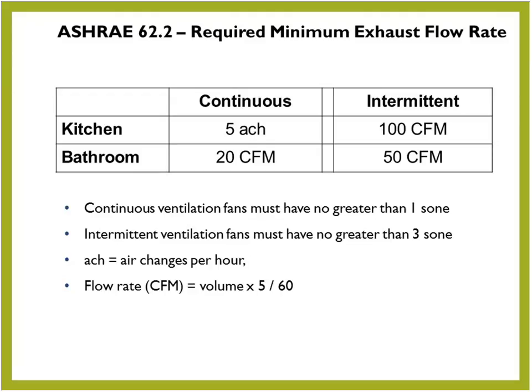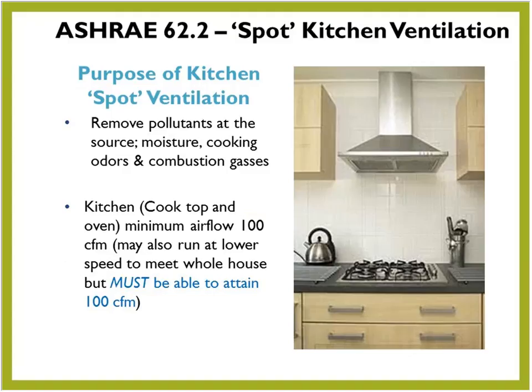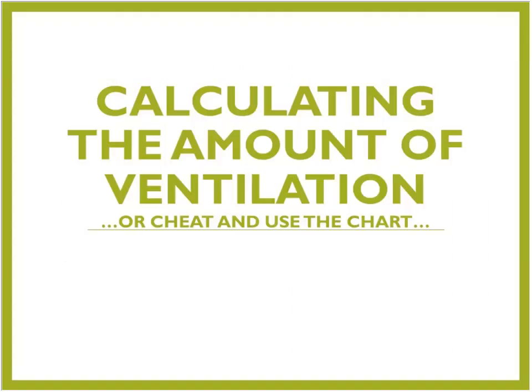Quickly, in terms of sizing those bathroom fans, there's a couple of different ways to do it. We recommend 1 CFM per square foot for the bathroom in order to exhaust that moisture quickly enough. There's other ways too, like you see here, the calculation V times 5 over 60. So the volume, length times width times height of the bathroom, times 5, and you're going to buy that fan in CFM, cubic feet per minute, so you want to divide that by 60. All right, kitchen ventilation, again, we want to make sure that it's minimum 100 CFM, and with any of these things, we want to make sure that they're quiet enough that people will actually use them. So that's a big consideration as well.